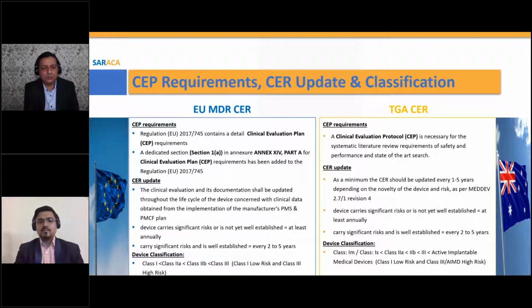For the TGA, the clinical evaluation protocol is necessary for a systematic literature review of safety and performance requirements and the state-of-the-art search. In the EU MDR, the regulation 2017 contains detailed clinical evaluation plan requirements. A dedicated section in its annexure, Annex 14 Part A, for clinical evaluation plan requirements has been added to the regulation.